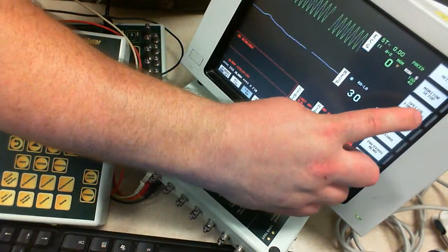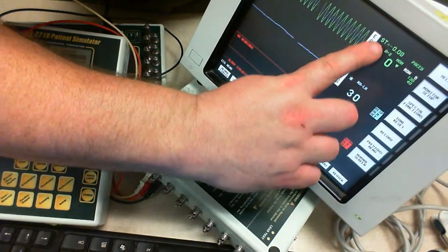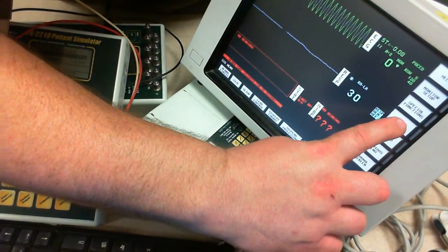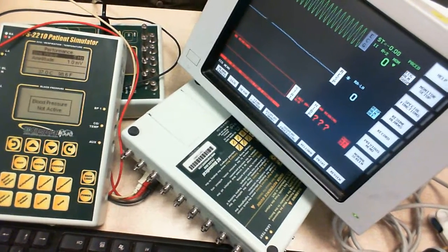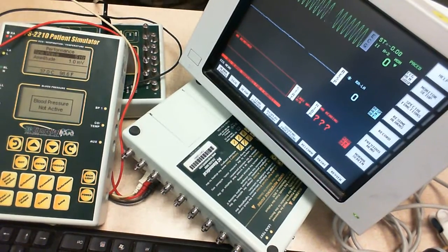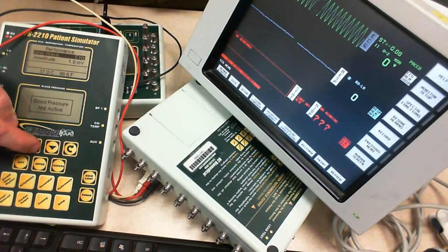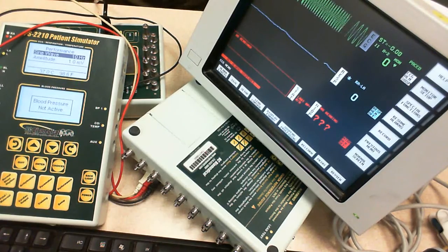I'm going to go ahead and suspend alarms since we've looked at this. What you do is tone reset, suspend alarm. There we go. So the alarm is suspended now. What we're going to do here is increase the frequency. Notice it's letting 5 hertz through. It's going to let 10 hertz through. You are essentially a 5 to 10 hertz machine.